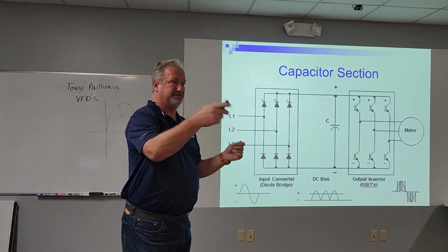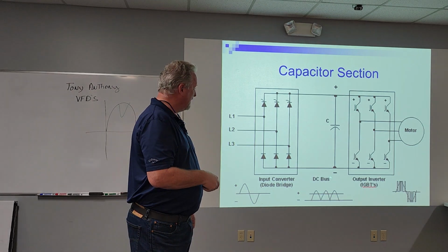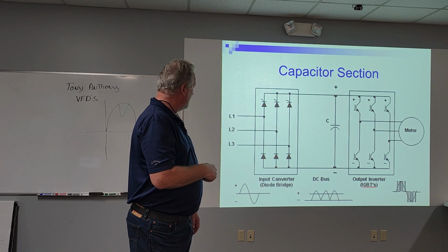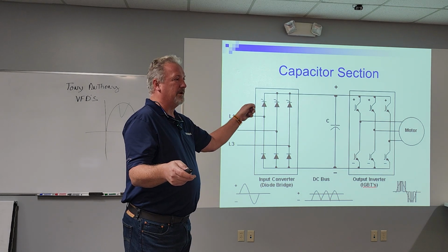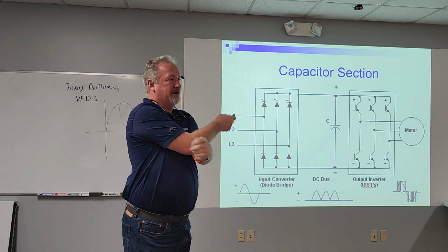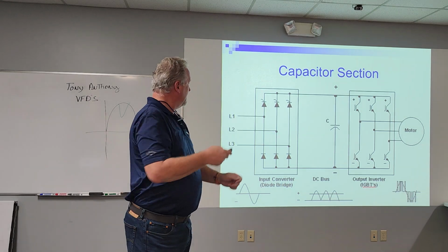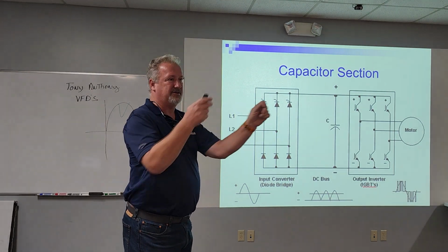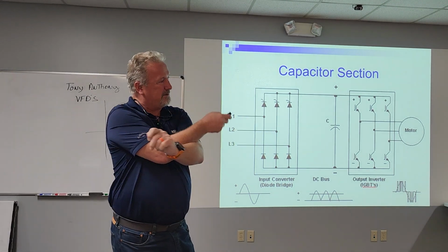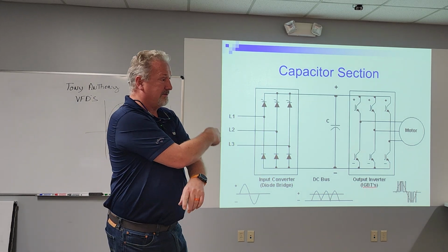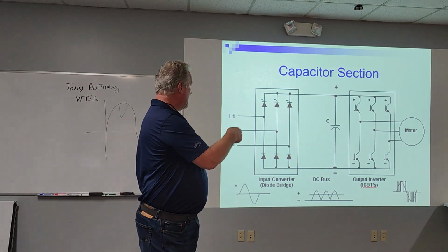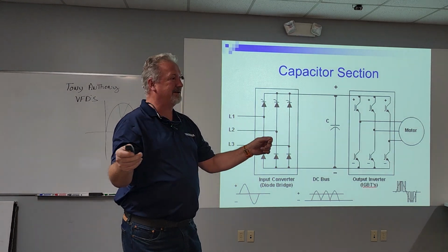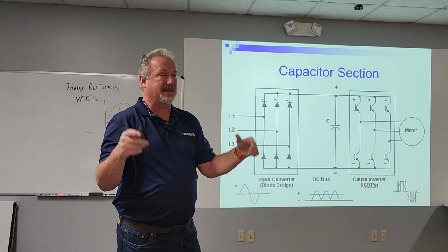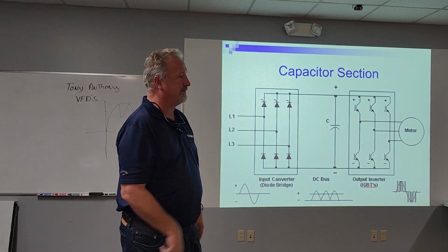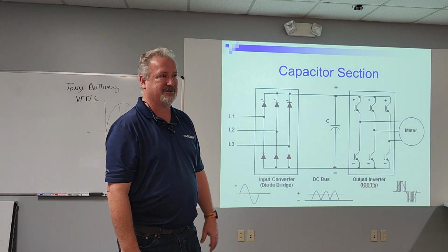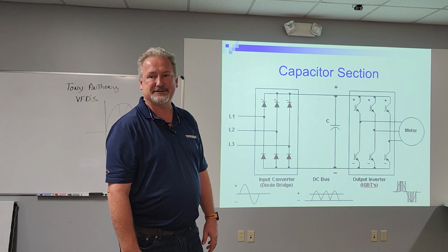Then you take your multimeter and put it on diode. You put one lead on minus and one lead on L1. Check it. One way it should show open, the other way you should get your beep. You do it for L1, L2, L3 to minus, and you check it both ways. One way should be open, the other way should be a beep. If you get that on all three, then you know the negative side is good. Take that, go to the plus, and do the exact same thing. That's how you can check the entire input section of the drive, just by checking it with a diode checker. Pretty simple, pretty easy.